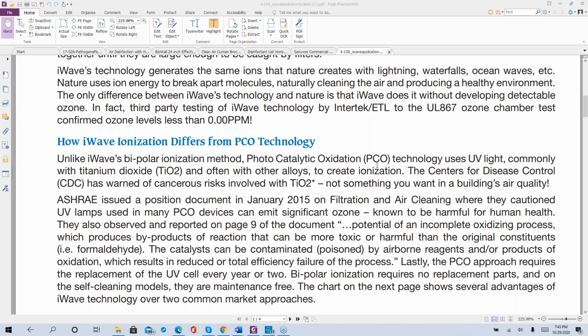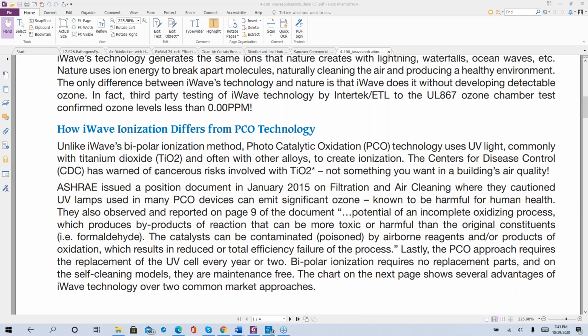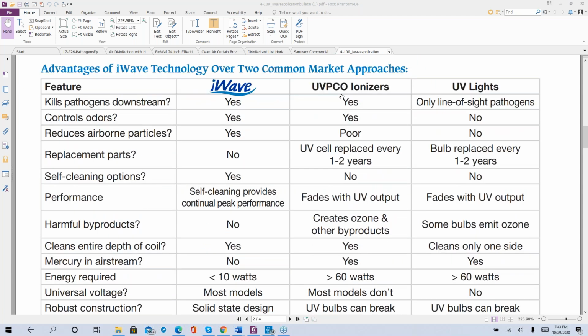The other technology is the PCO, or photocatalytic oxidization, and that's the titanium dioxide. And that is also another one that is prevalent to breaking down and creating some dangerous, not nearly as much that the EPA would be concerned, but any ozone is bad ozone in my eyes. So this is how they are comparing the UV light. Only the line of sight pathogens, that is a true statement. Downstream, controls odors. UV light will, if they put in UVV as in Victor light. Airborne particles, yes. Airborne particles like dust and dirt, it's going to zap them.